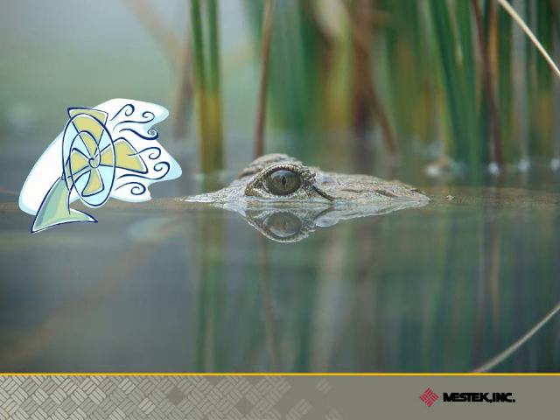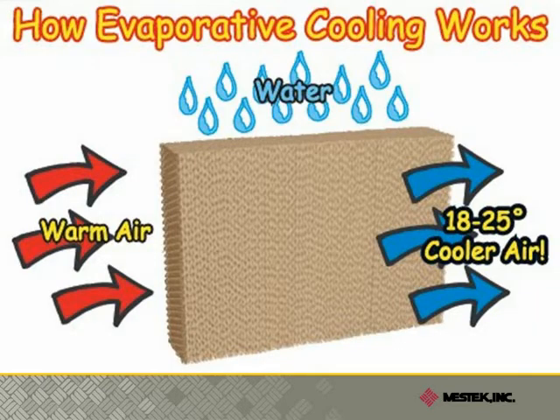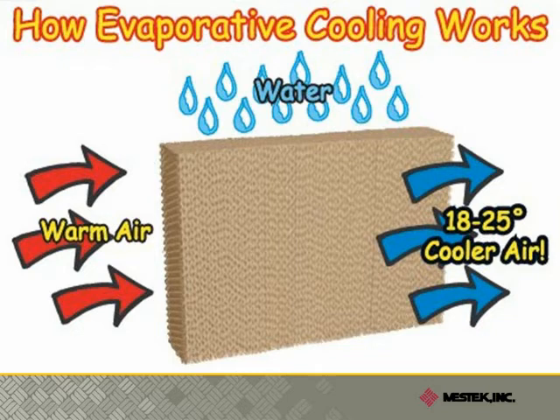We have a way to help offset some of that problem, using a technology sometimes identified by the less-than-complimentary term 'swamp cooler.' Swamp coolers are actually evaporative coolers, and the concept is quite simple. If you take warm air and pass it through a porous pad soaked with water, you can get much cooler air out the other side. Water has a large capacity for absorbing heat as it transitions from liquid to vapor — the warm outside air provides the energy to cause that transition and gives up large amounts of heat in the process.